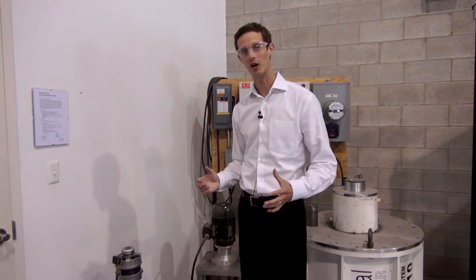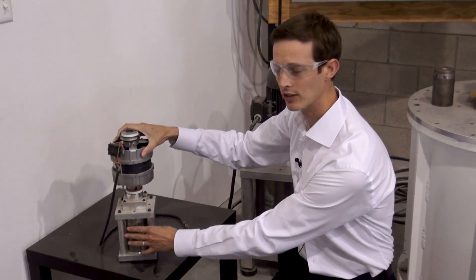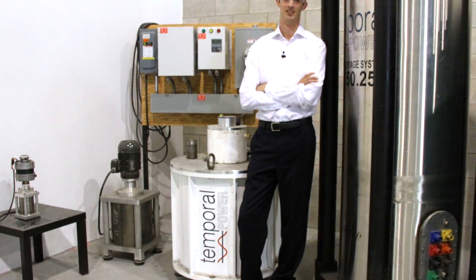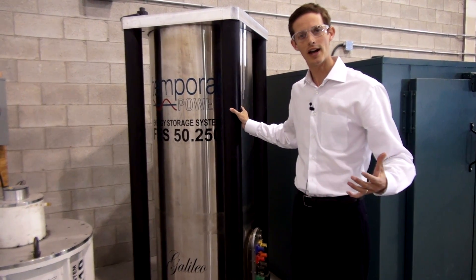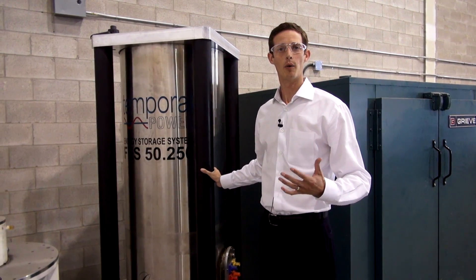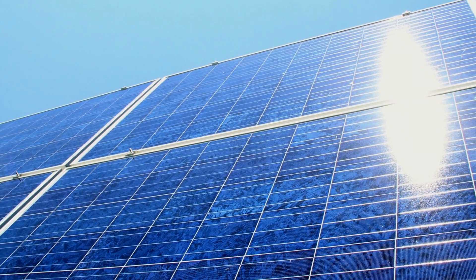The first version of the flywheel is a desktop prototype that inventor Geoffrey Valtteri made in 2009. It is a solid steel flywheel levitated by a fully permanent magnetic bearing system, able to store energy efficiently over long periods of time. From this lab bench version, Carver and inventor Geoff Valtteri scaled the flywheel up three more times. The current system is the world's highest energy, highest performance flywheel energy storage system — almost seven feet high, weighing about 9,000 pounds, and storing 50 kilowatt hours of energy, about the same as two Chevy Volts. The large flywheel can store excess energy when the sun shines and release it when the sun goes behind the clouds.